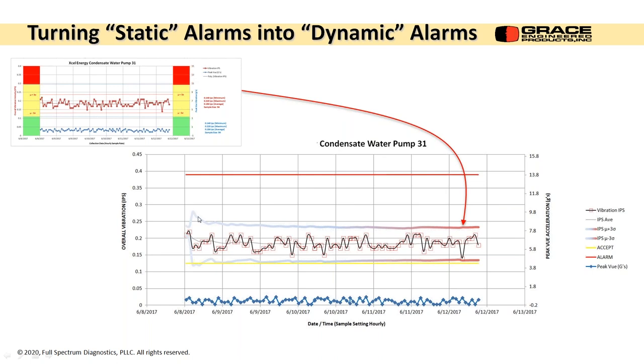The gray was initial, the first couple hours, and it's pretty ragged. Then all of a sudden it starts zeroing in on a much better statistical alarm level. And this is only 4 days. I think it's phenomenal for just basic vibration monitoring. You still need to get a spectrum and a waveform, but it's telling us a lot more than we think it is. I was just using basic statistics and having them update every hour, and it gets a really nice trend.